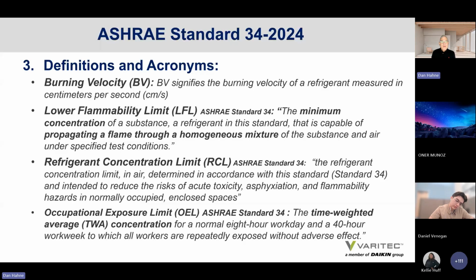Before we begin looking into Standard 34, let's make sure we have a common understanding of certain definitions and acronyms. We need to understand what burning velocity is. BV signifies the burning velocity of a refrigerant measured in centimeters per second. We need to understand what the term lower flammability limit means, or LFL. It is the minimum concentration of a substance in which a flame can propagate throughout a homogeneous mixture. So it is the lowest concentration limit that will support a flame throughout the mixture.